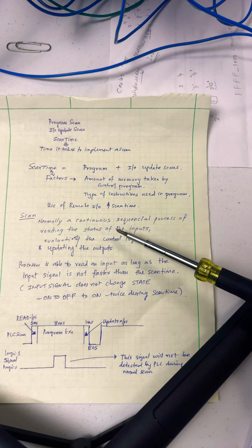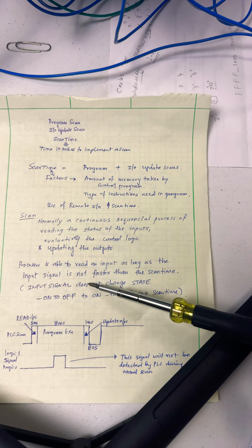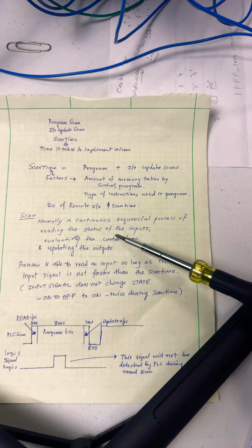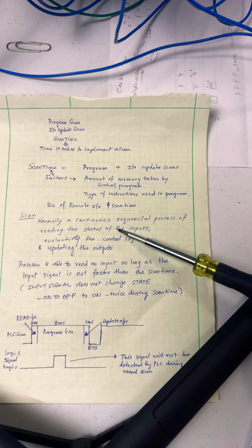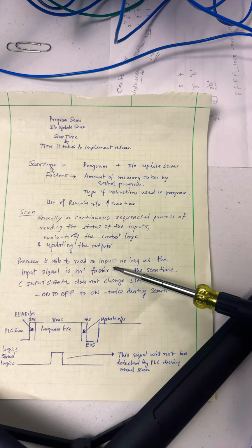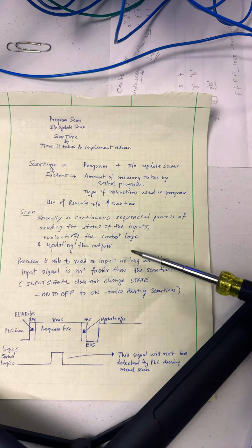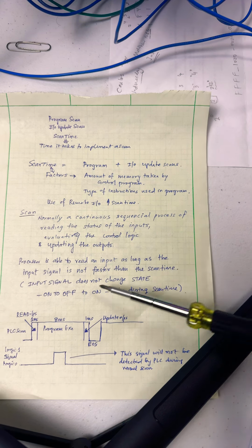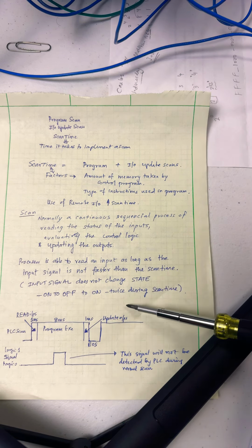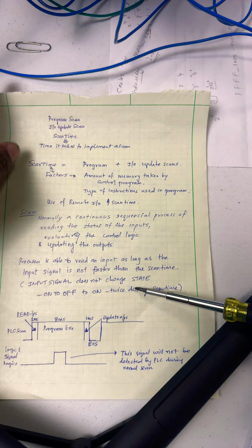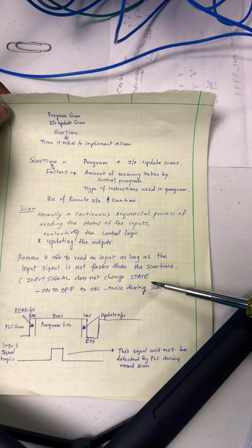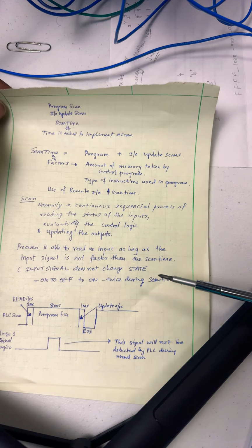scanning, a continuous task. One of the challenges with continuous scanning is that the processor will be able to read an input as long as the input does not change faster than the scan time.